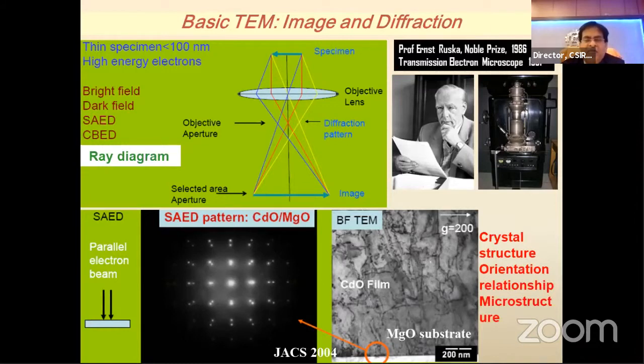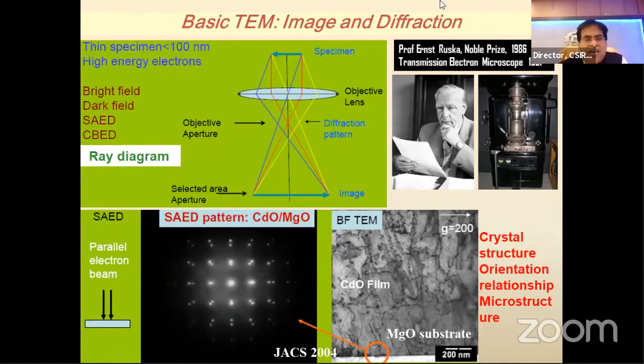Coming to the transmission electron microscope: in SEM we look at surface microstructure and surface chemistry, but in TEM the electron beam passes through the specimen, so the specimen must be very thin — around 50 to 100 nanometers for routine TEM, and 5 to 10 nanometers for atomic-scale microscopy. The most important modes are bright field, dark field, selected area electron diffraction (SAED) in reciprocal space, and convergent beam electron diffraction (CBED) for understanding symmetry.